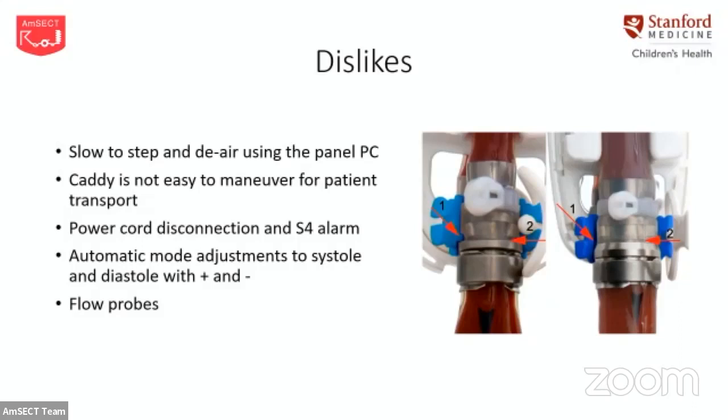Or we've seen it where the cord is unplugged from the wall, but then maybe you're just untangling something, plugging it back in right away, and it'll alarm at you for that as well. So they've told us you have to wait 10 seconds if you unplug before you plug it back in. But that S4 alarm cannot be cleared. You have to exchange the driver out and send it back to Berlin. So it's kind of a pain when you run into that alarm.